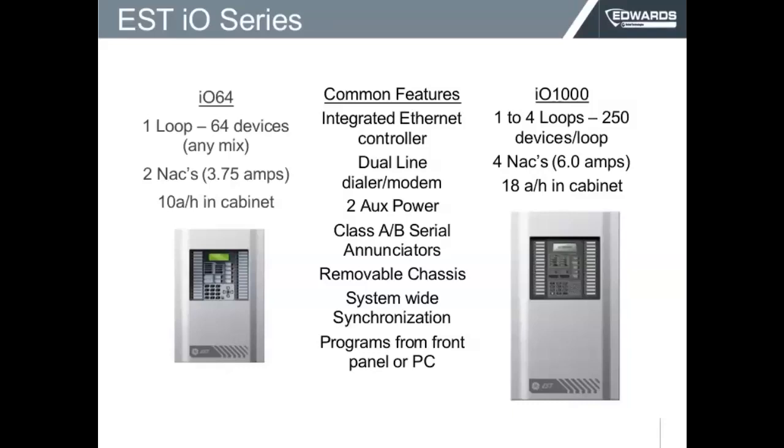The iO1000 is one panel that has one loop of 250 devices — that will be 125 detectors and 125 modules — and it can be expanded from one loop to four loops. The iO1000 has four NAC outputs of up to 6 amps, and the cabinet can have batteries up to 18 amp hours.